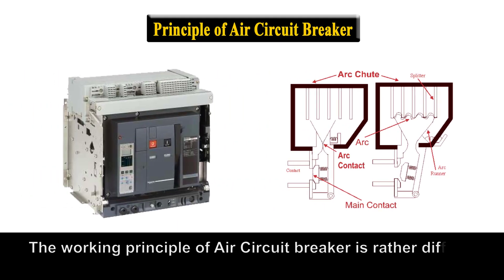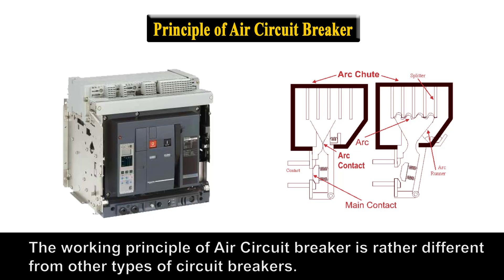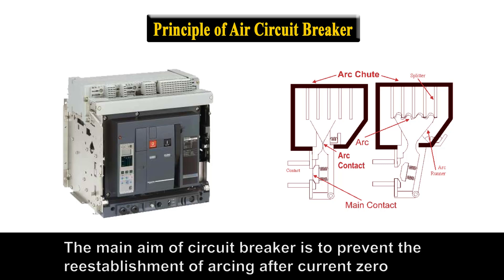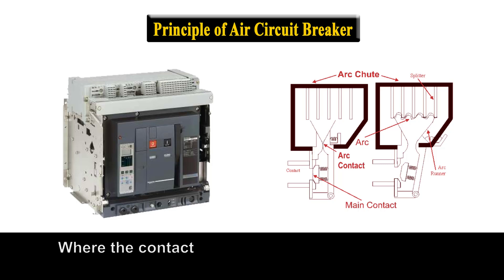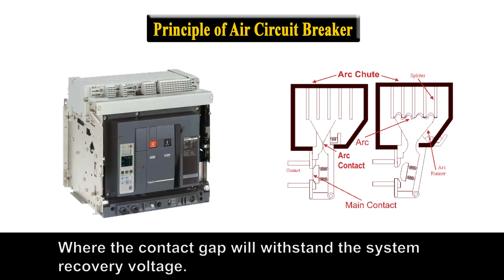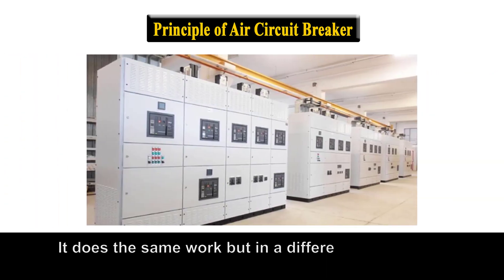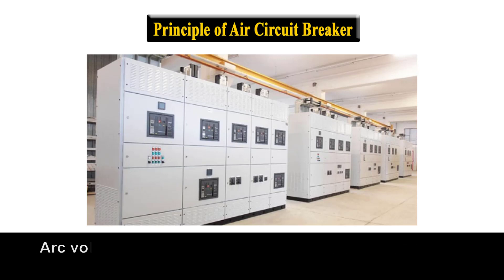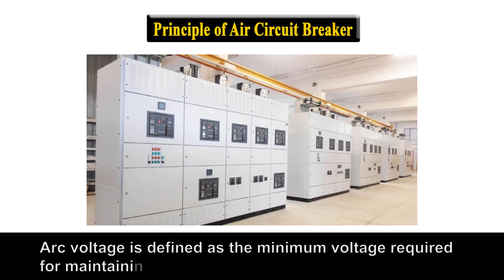The working principle of Air Circuit Breaker is rather different from other types of circuit breakers. The main aim of the circuit breaker is to prevent the re-establishment of arc after current zero, where the contact gap will withstand the system recovery voltage. It does the same work but in a different manner. During the interruption of arc, it creates an arc voltage instead of the supply voltage. Arc voltage is defined as the minimum voltage required for maintaining the arc.